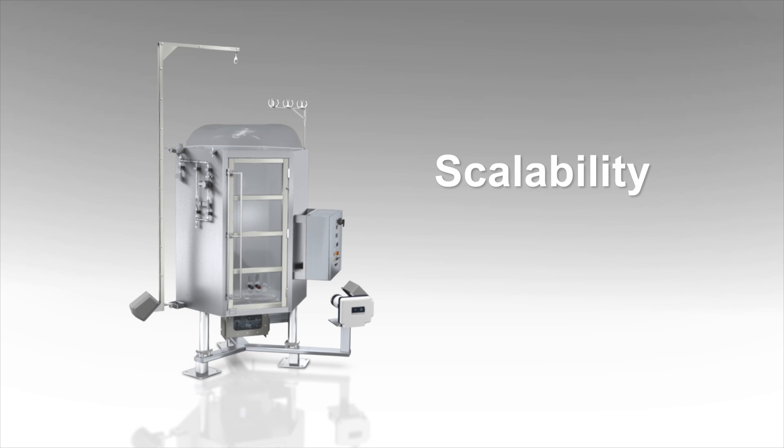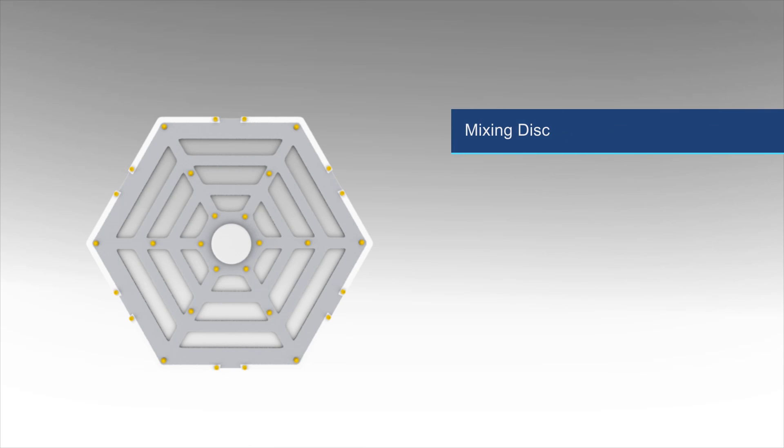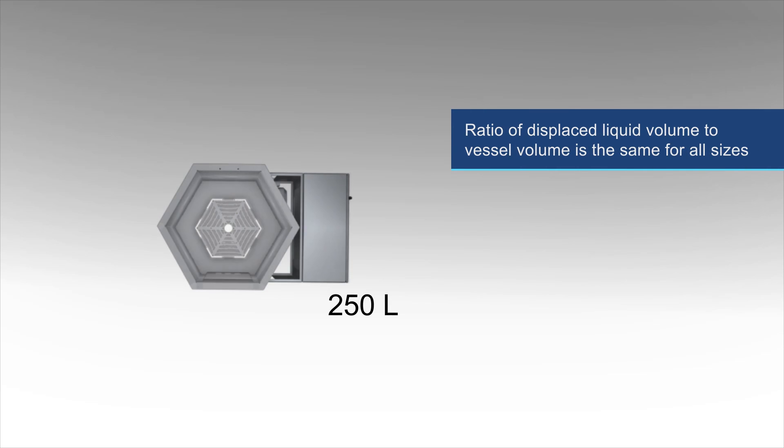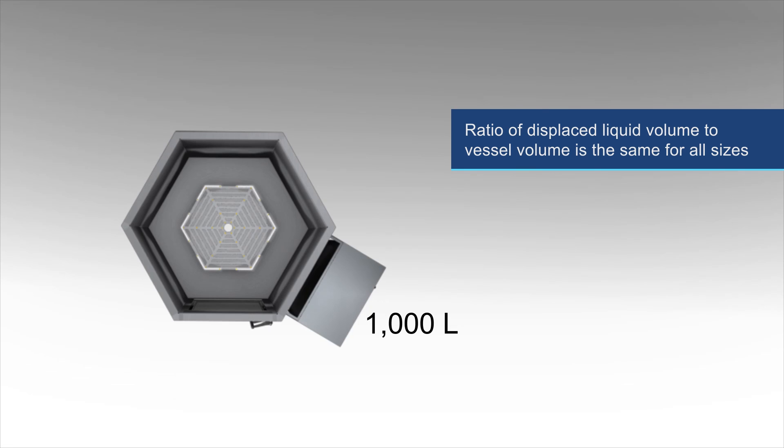The Impulse single-use mixing system is designed for scalability. The mixing disc diameter increases proportionally as the size of the vessel increases. The ratio of the displaced volume of liquid during the downstroke of the mixing disc and the overall vessel volume is the same for all mixer sizes.